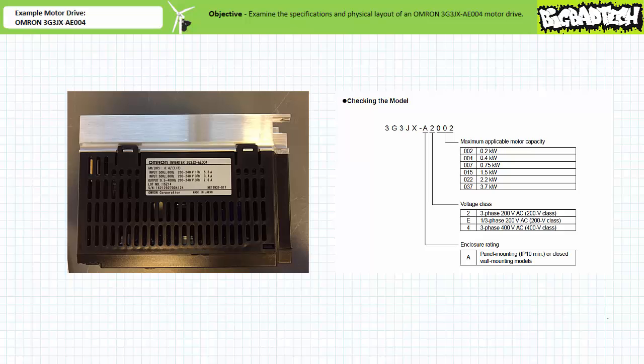The nameplate further specifies this value could be 200 to 240 volts as well as indicates current draw for a given input condition. The motor capacity entry of 004 specifies this drive is intended to operate a 400 watt or roughly half horsepower motor.